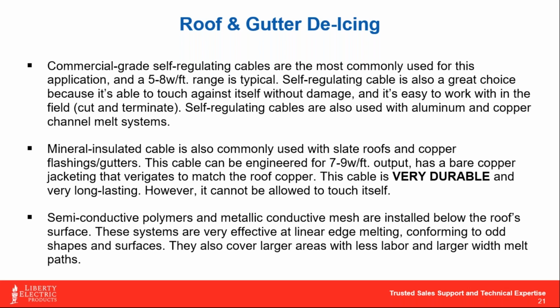Mineral insulated cables are pretty popular for roof and gutter because we get to engineer the wattage output of that cable. We can design an MI cable to put out exactly 8 watts a foot, or somewhere between 8 and 9 watts a foot, which could be totally safe and fine on a slate and copper roof.